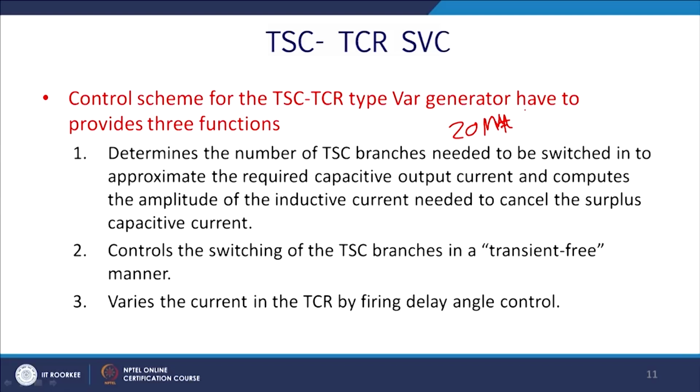So, what should be the one branch's capacity of compensation. Let us say we decide, with all the constant thyristor ratings, transients, all those considerations put into the operation, that 2 MVA will be suitable.